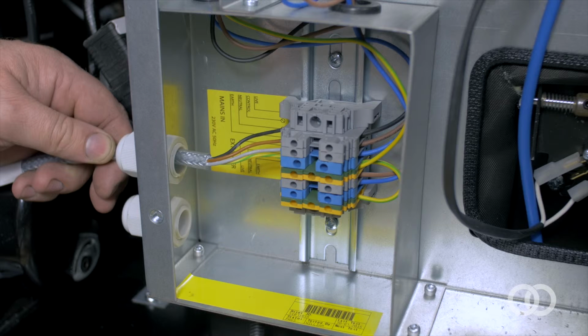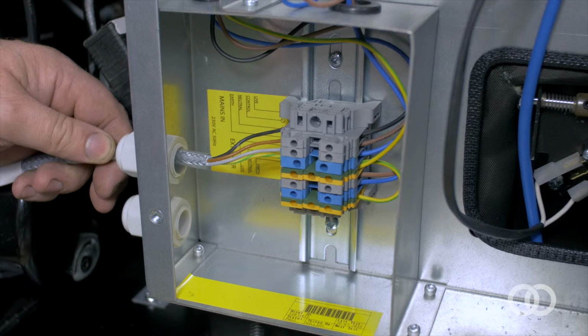A 4-core cable needs to be connected to the boiler. Black is permanent live. Brown is time clock or controlled live. Blue or grey is neutral. Green and yellow is earth. The appliance must be connected to an electrical system which is equipped with an earth conductor complying with CEI 64-8.